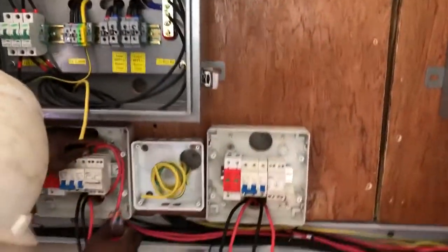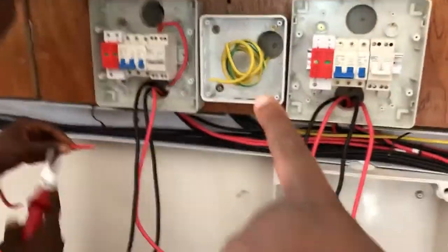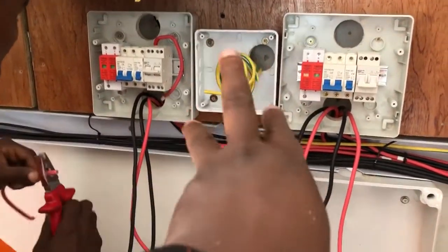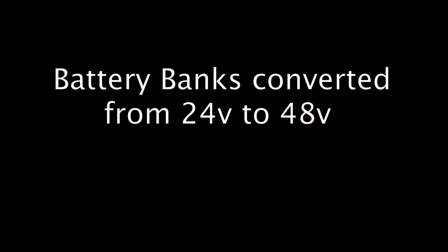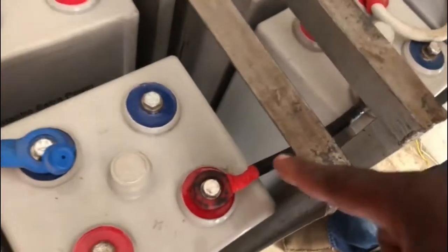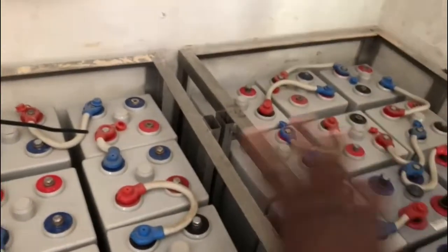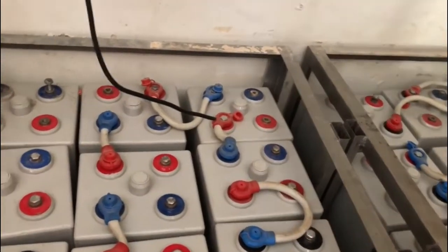Things are at an advanced stage now, with all the wiring off and going. We've got an earth box there, where all the grounding meets and then sends down to the main earth conductor through there into the ground at the back. So we've basically now got to the battery stage, and the two banks have now been connected with that thick connector there. So now we have a 48 volt battery bank instead of two 24 volts.